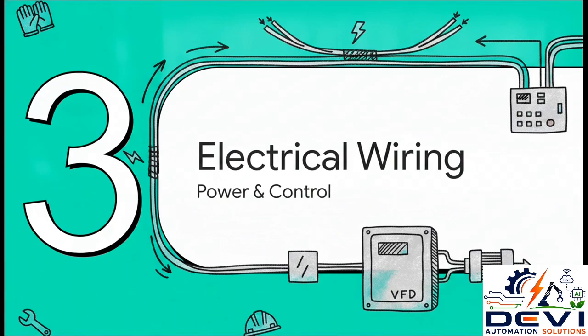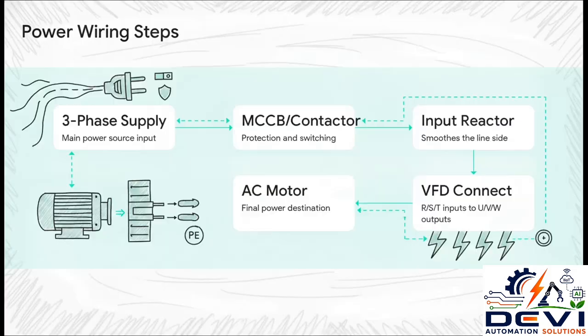Now for Section 3, electrical and control wiring. Think of the chronological power wiring sequence kind of like a river of current. You start at the three-phase supply. From there, power flows into your MCCB and optional contactor for protection and switching. Next, it routes through the input reactor to smooth out the line side. Then it finally lands on the VFD inputs, your R/L1, S/L2, and T/L3 terminals. From the VFD, the modulated power exits via the U, V, and W terminals straight down to the motor. And obviously, every step of the way, you absolutely must tie into that PE, or protective earth terminal.